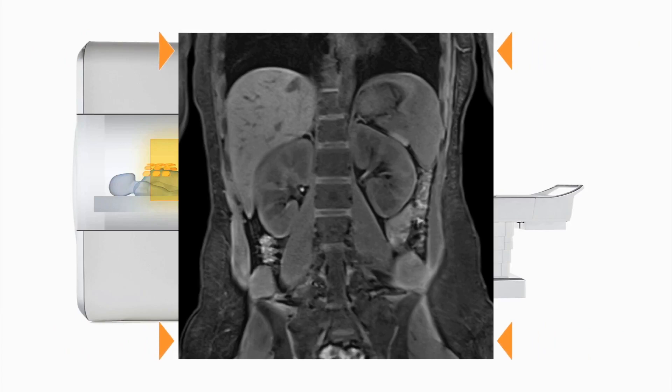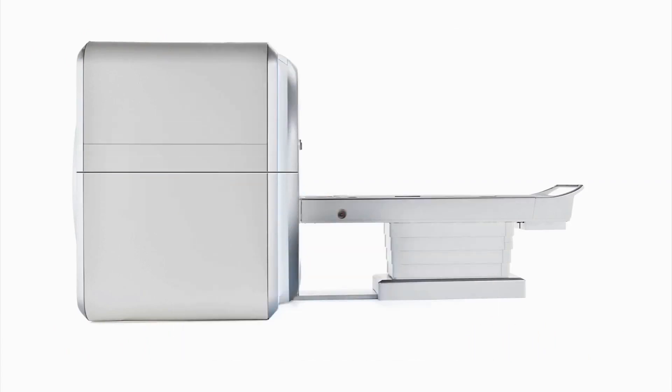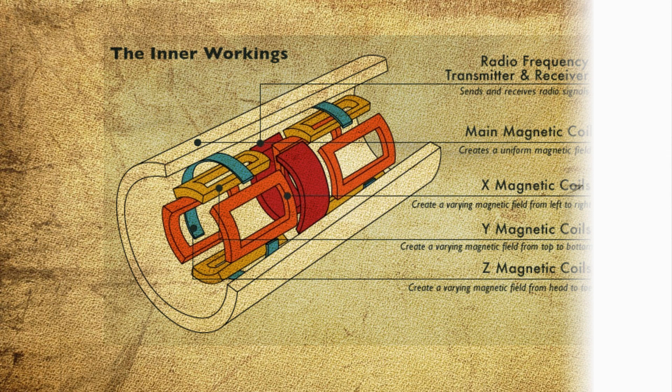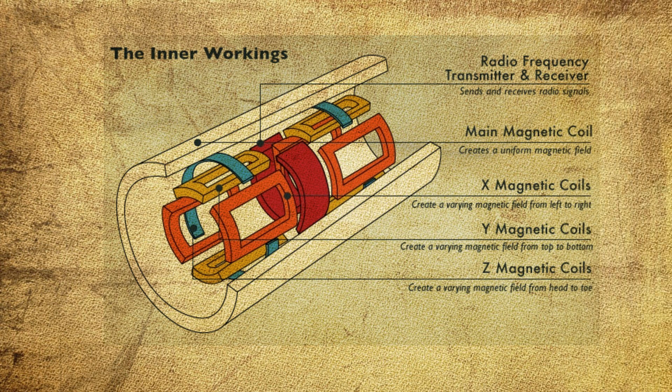The first component is magnets in the MRI machine. The magnet is the largest and most expensive component of the scanner, and the remainder of the scanner is built around it. The strength of the magnet is measured in Teslas, or T.